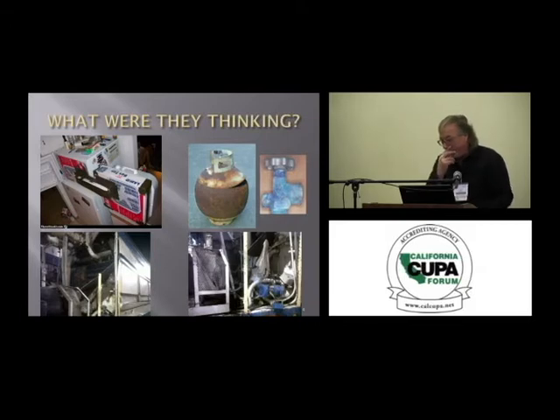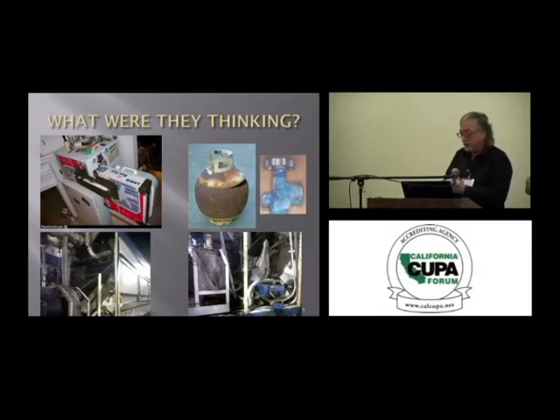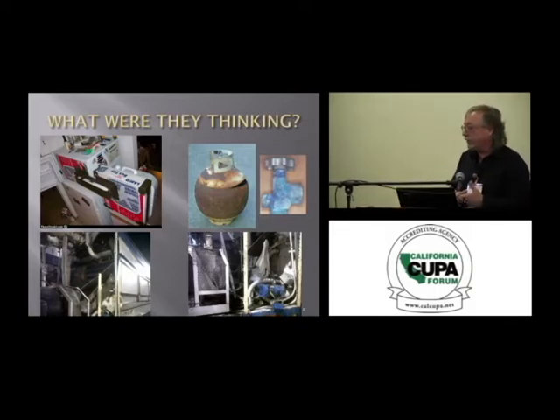The top right one, that was a mistake that a couple of meth dealers made in Florida. They stole some ammonia from a facility, and you'll see this if you see anything like this around plants. Valves that are green like this on the right, tanks, hoses, clamps, plugs or caps missing from orifices outside, such as on a high pressure receiver. Most of the time what we find is that somebody's stealing the ammonia. They use it to cook methamphetamine. Unfortunately, ammonia is a refrigerant.